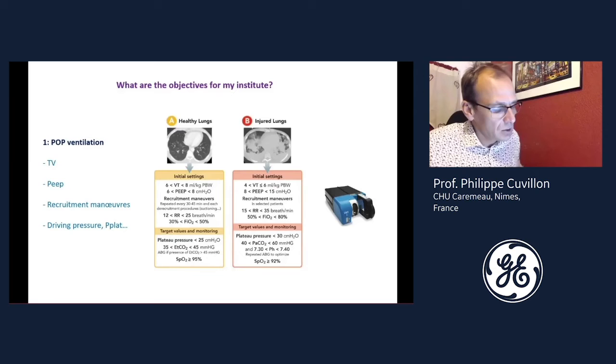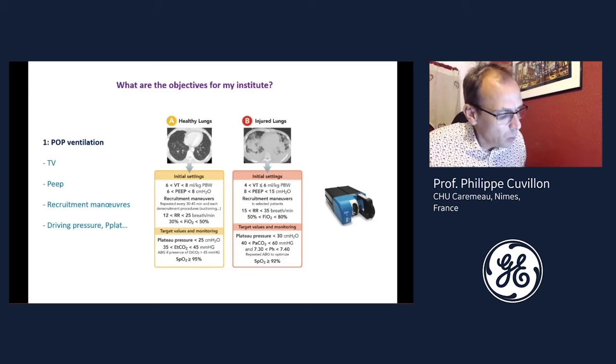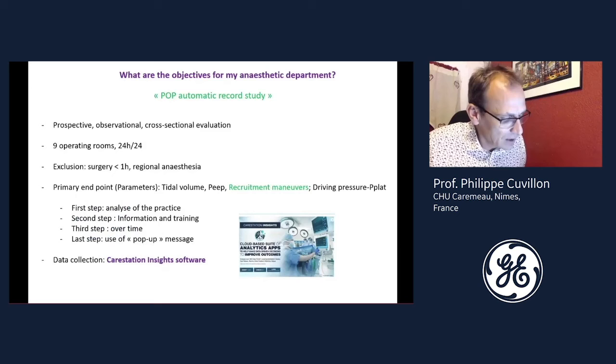The next step is to know what can be done with this computer system. The objectives we set were to evaluate the practice of protective ventilation and recruitment maneuvers in our establishment and to improve its performance by using the Carestation Insights application. To do that, we conducted a prospective study including nine operating rooms, the results of which were presented last year and are currently being published. The main objectives were to improve ventilatory parameters in accordance with the recommendations: tidal volume, PEEP, recruitment maneuvers, driving pressure, and plateau pressure.